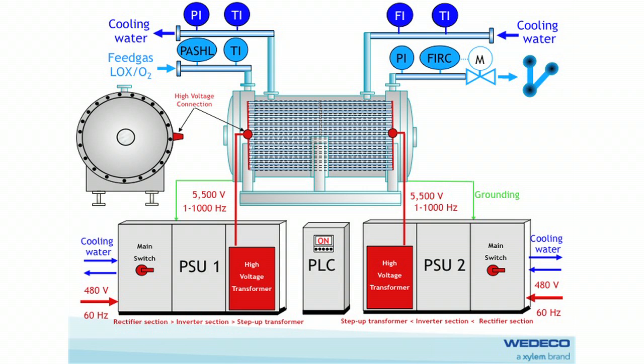Also unique on our system is the 2 power supply units, particularly on our bigger generators. We run at 2 PSUs. Each power supply unit is capable of producing up to 60% of the design capacity of the whole generator. Generators generally don't fail, while our systems do not fail. What tends to happen is you have electrical problems, and so the faults generally lie in the, oops, seems a bit touchy. So generally the power supply problems cause most of the trips in these generators. So having redundancy on your power supply allows you to still carry on running up to 60% of your capacity of a single power supply while the other one is repaired.